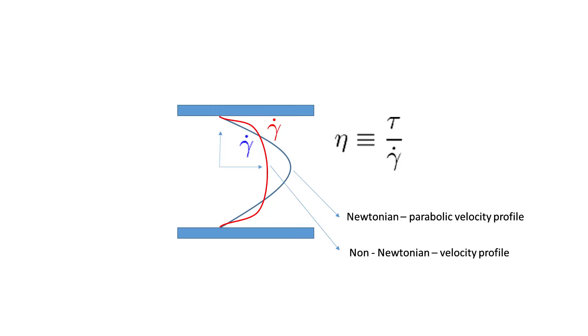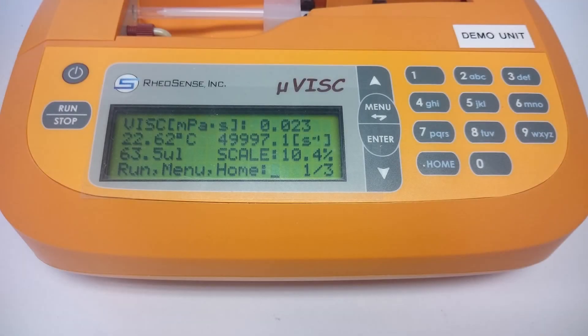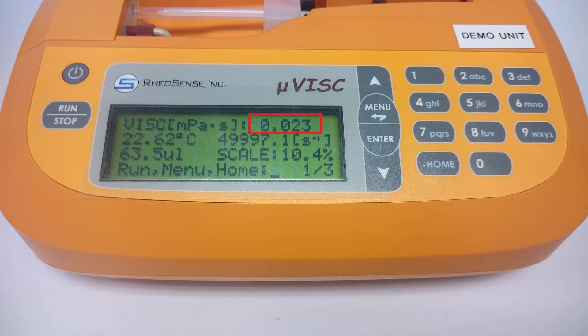Other than affecting the shear rate range, non-Newtonian samples also change how we want to analyze the data. For a Newtonian sample, the viscosity value displayed by the instrument is the true viscosity. No additional work is required.